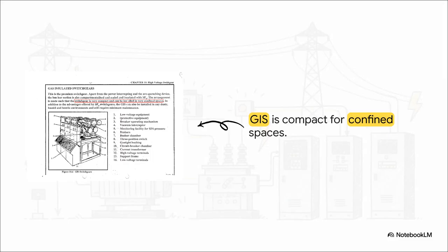And that brings us to the first major solution: gas-insulated switchgear, or GIS. It's a highly compartmentalized, metal-clad dead tank design. By using GIS, you can safely pack massive, extreme voltage power switching capabilities into incredibly confined indoor spaces. It completely transforms the whole concept of a high-voltage substation. It literally turns what used to be a massive outdoor yard into just a sleek, compact building. It's a real game changer.